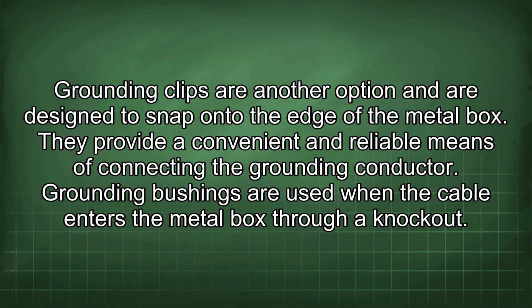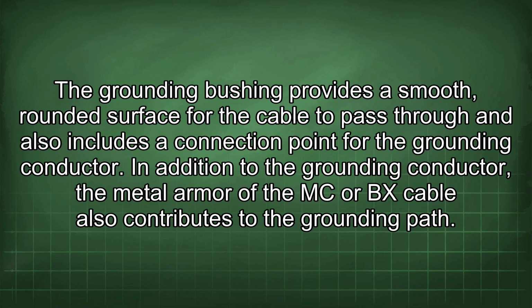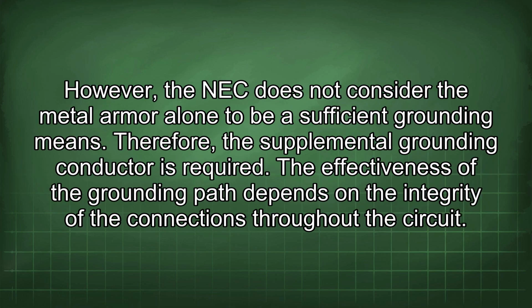Grounding bushings are used when the cable enters the metal box through a knockout. The grounding bushing provides a smooth, rounded surface for the cable to pass through and also includes a connection point for the grounding conductor. In addition to the grounding conductor, the metal armor of the MC or BX cable also contributes to the grounding path. However, the NEC does not consider the metal armor alone to be a sufficient grounding means. Therefore, the supplemental grounding conductor is required.